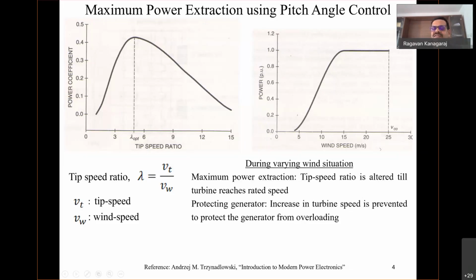We don't want the generator overloading. That is connected with the machine we've already installed, meant for a certain rating, a certain power. So now if excess mechanical power comes, it cannot be converted into generated electrical power because the windings would carry more current. So we don't want excess mechanical power, and the turbine blades get adjusted such that the additional mechanical power is not available. Only whatever conversion was done up to 15 meter per second, that conversion only you are getting.